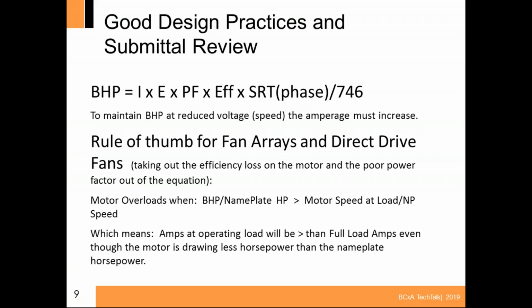At 66% speed, the voltage is so low that the amperage has got to surge very high to create the same amount of brake horsepower. Brake horsepower is in this first equation on top. So the moment he starts it and dials it back, that motor will never work. It'll always overload because that fan requires too much brake horsepower. He's trying to slow the motor down with the drive. It will never happen. Now, if you had a belt drive, you could just re-sheave it. But in this case, we have a direct drive.